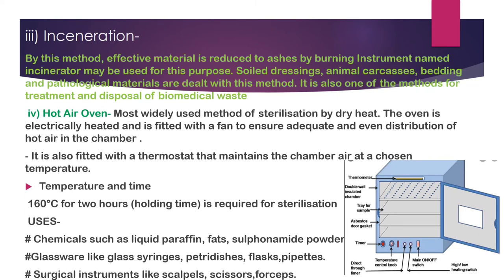The next method is the hot air oven, which is the most widely used method of sterilization by dry heat. The oven is electrically heated and has a fan to ensure adequate and even distribution of hot air in the chamber. It is fitted with a thermostat to maintain the chamber air at a chosen temperature. The temperature and time required is 160°C for two hours as the holding time.